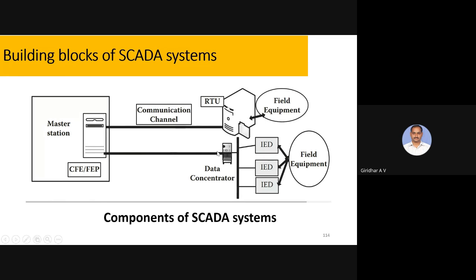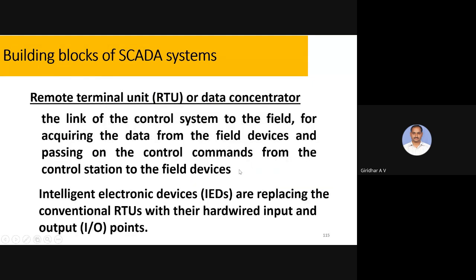So you can see field equipment. RTUs nowadays, in very high voltage substations, IEDs are preferred. From the IED, monitoring, control, and protection aspects are handled using multifunction relays, and the data is passed to the data concentrator and master stations as well. Now if you look at RTUs, remote terminal units.